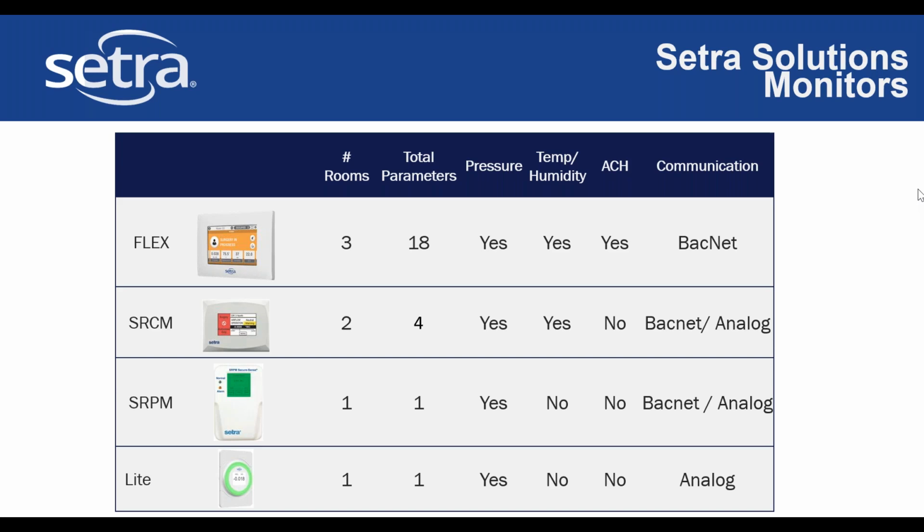We have a question regarding all the pressure monitor types you showed: do they have the same reading time from the sensor? So I think this is maybe around where the pressure sensor is. On the majority of the room monitors that we showed here, the pressure sensor is actually on board the monitor, so you have a real-time reading of the pressure value. There is one option on the Flex to have an external pressure sensor that is not on board the monitor, and you will be taking the real-time data as well.